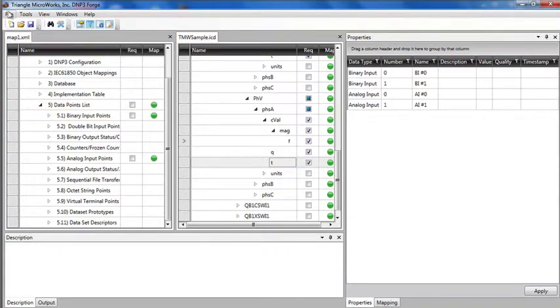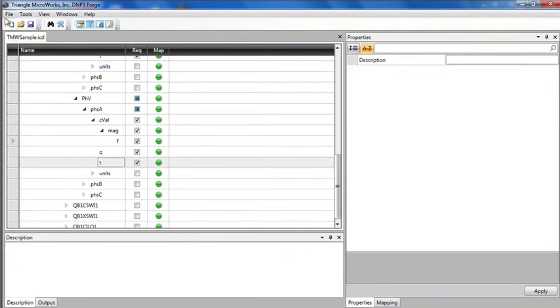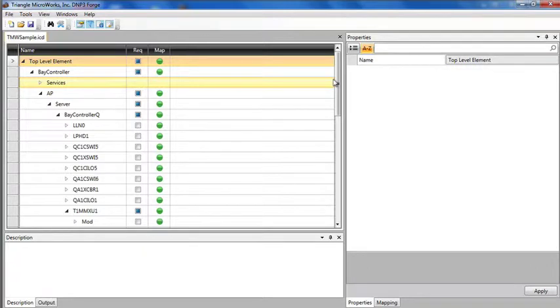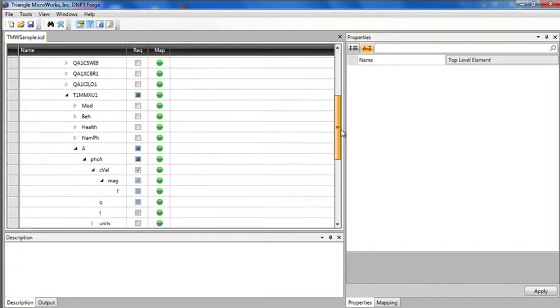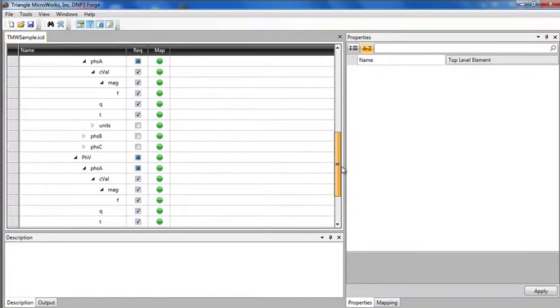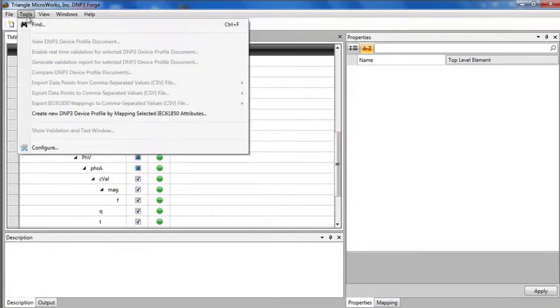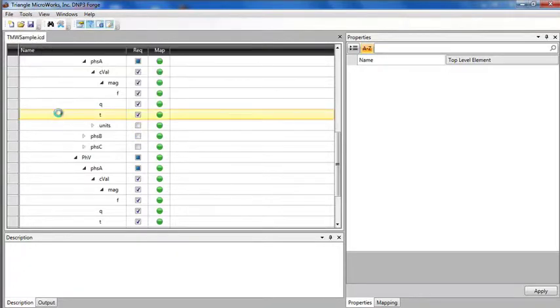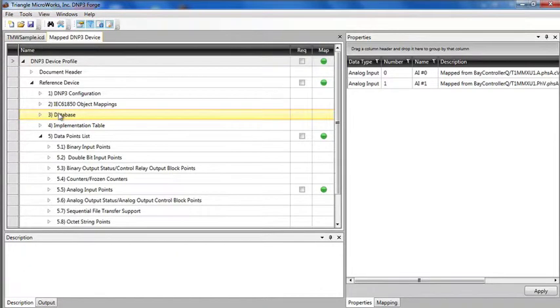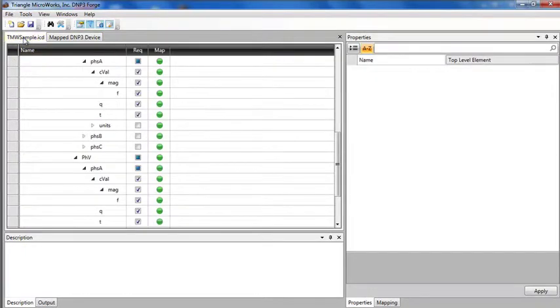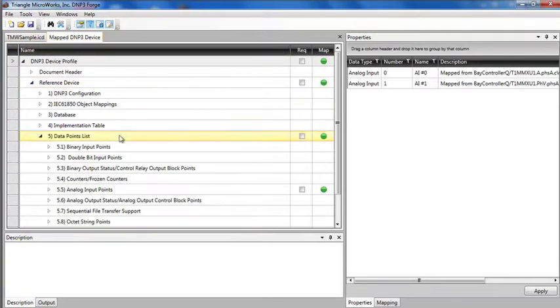I'll close it and show another way to create device mappings. Here I have the same ICD file I was working with before, and notice I still have checked the values that are required to map. Now, I'm just going to go to tools, create new device profile by mapping selected IEC 61850 attributes, and it creates the new mapped file.